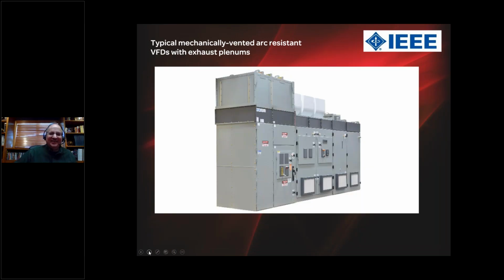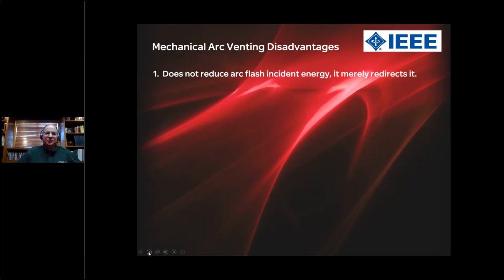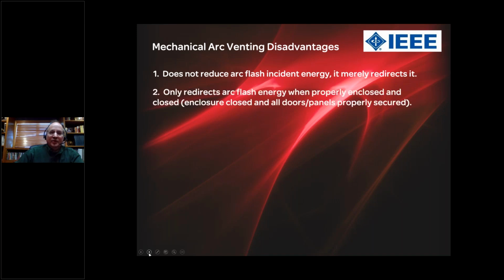Here's a picture of mechanically vented arc resistant variable frequency drives. This particular drive lineup is an Eaton solution. And you can see again the exhaust plenums on top of the equipment. So in terms of arc venting disadvantages, I call it the seven deadly sins of mechanical arc venting. One, it doesn't reduce arc flash incident energy compared to standard switchgear, not at all. It just redirects it. Two, it only redirects arc energy when it's properly enclosed and closed up. So the second you open one of those panels, if it's exposed energized, it's no longer arc resistant. And in fact, you have greatly enhanced risk at that point, because the arc energy is now directed toward the person standing in front of the open panel.